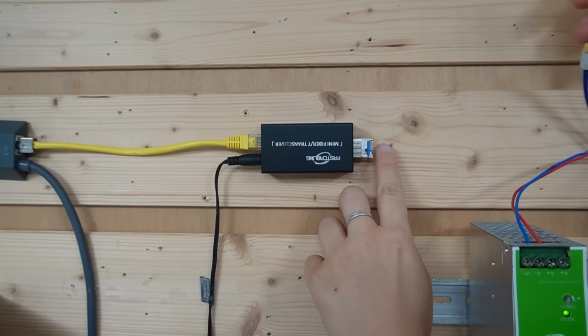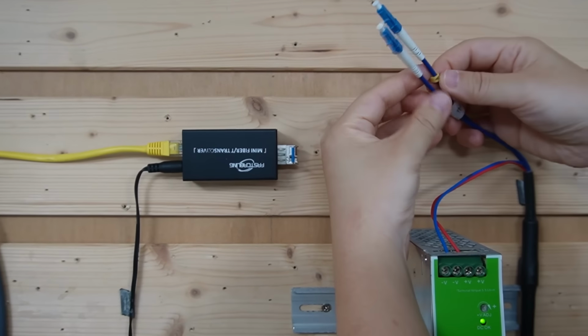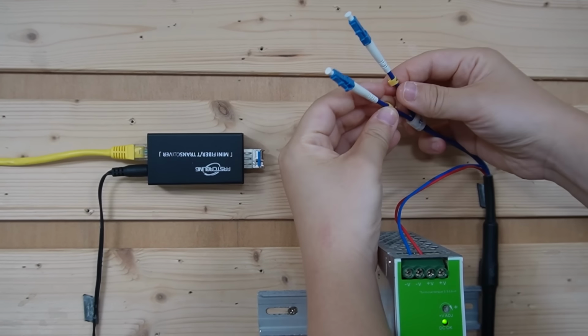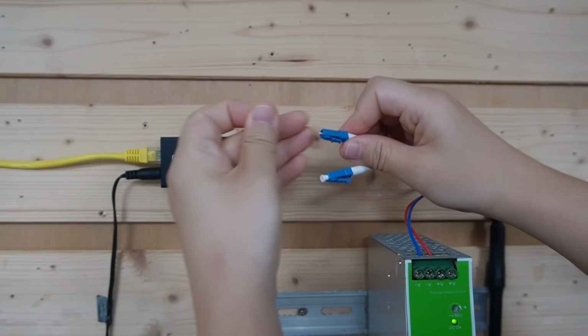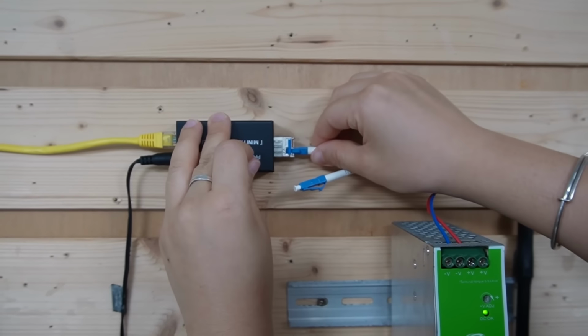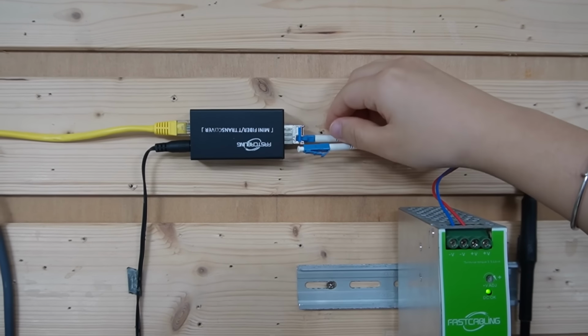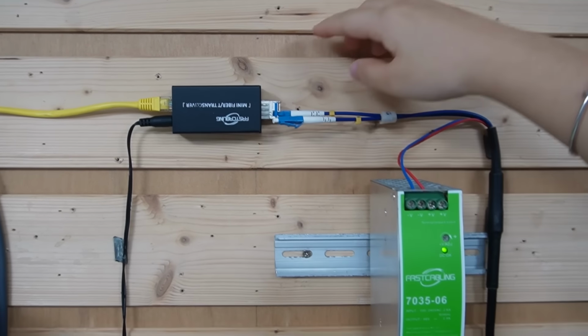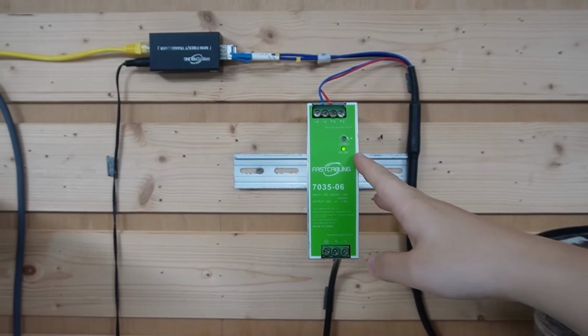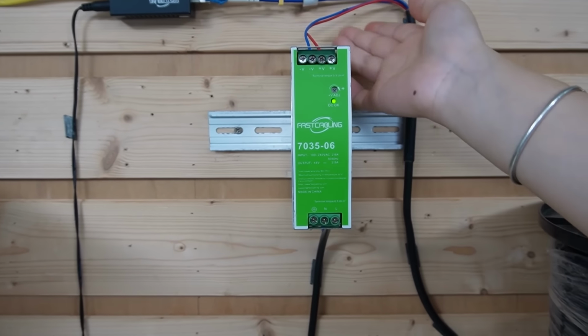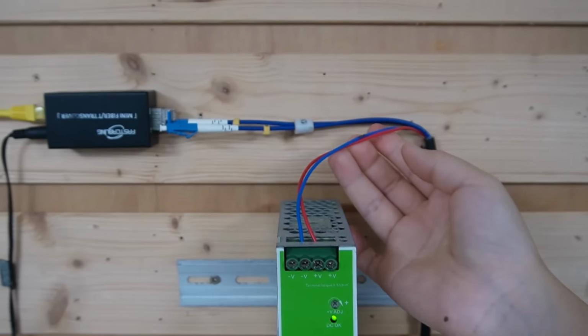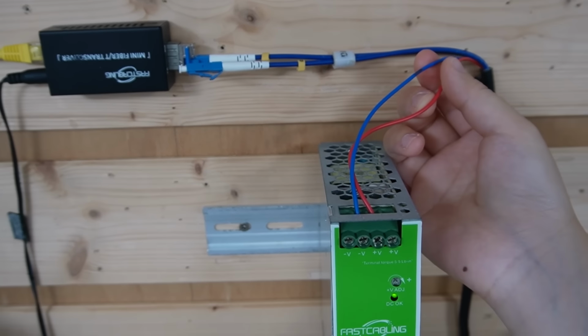This is where you connect to the fiber optic cable. Since we have 2 strings, let's use string A and leave string B as spare. Just plug it all the way in. And now for the power side, we recommend a DC composite cable; inside, alongside the fiber, are these copper wires.